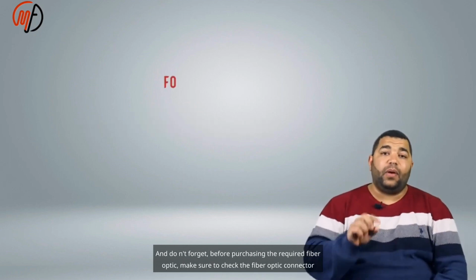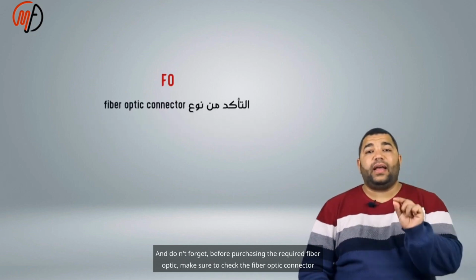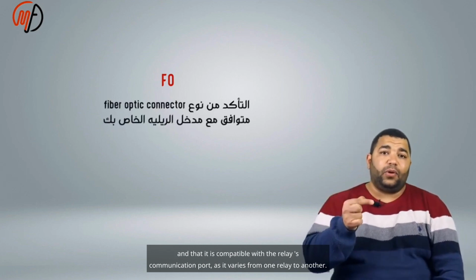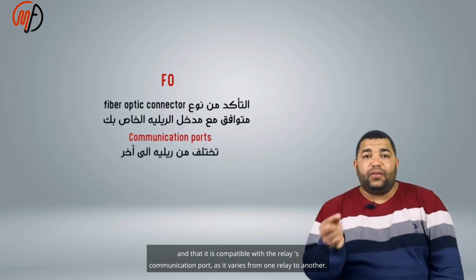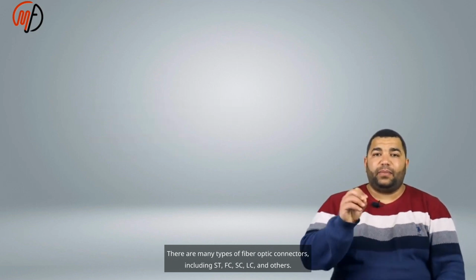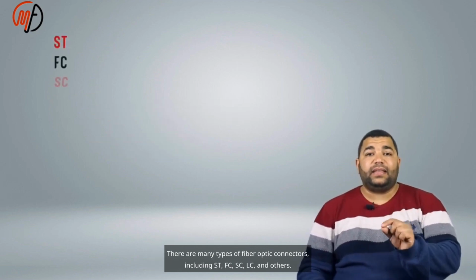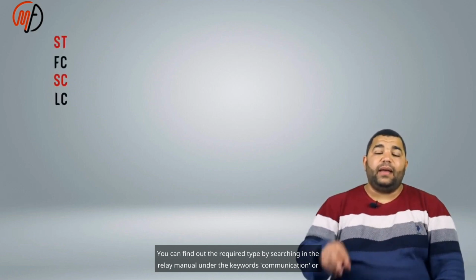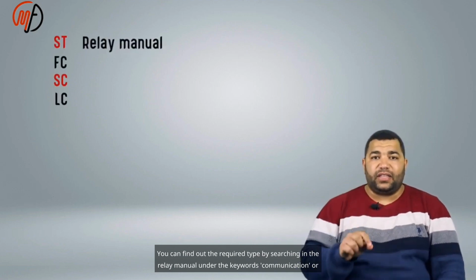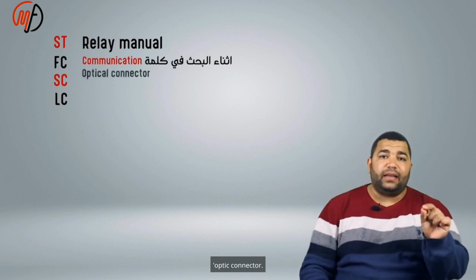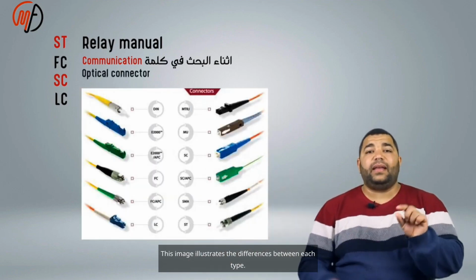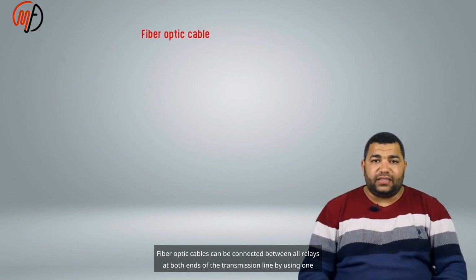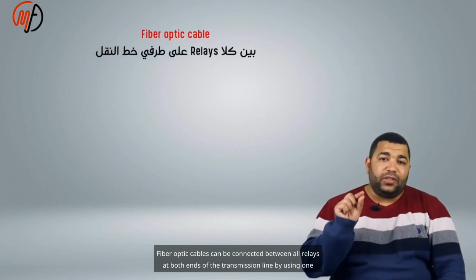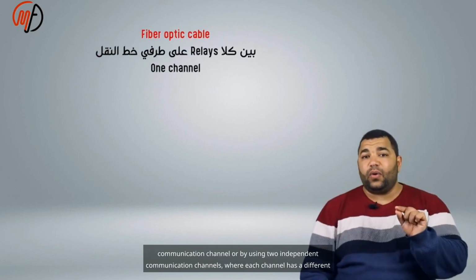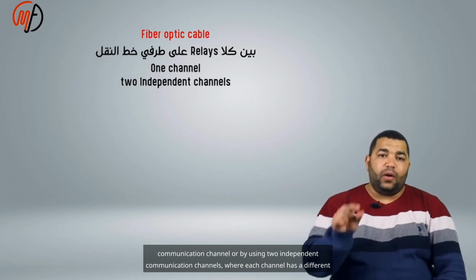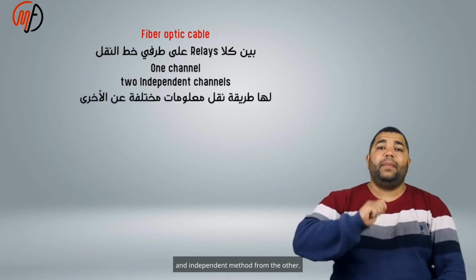And don't forget, before purchasing the required fiber optic, make sure to check the fiber optic connector and that it is compatible with the relay's communication port, as it varies from one relay to another. There are many types of fiber optic connectors, including ST, FC, SC, LC, and others. You can find out the required type by searching in the relay manual under the keywords communication or optic connector. This image illustrates the differences between each type. Fiber optic cables can be connected between all relays at both ends of the transmission line by using 1 communication channel or by using 2 independent communication channels where each channel has a different and independent method from the other.